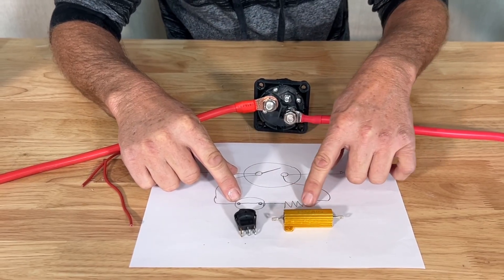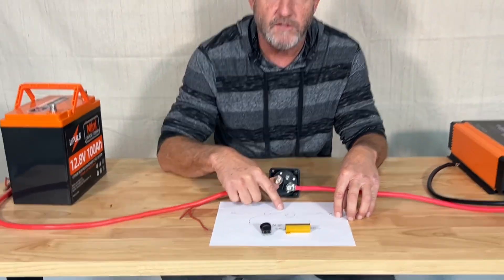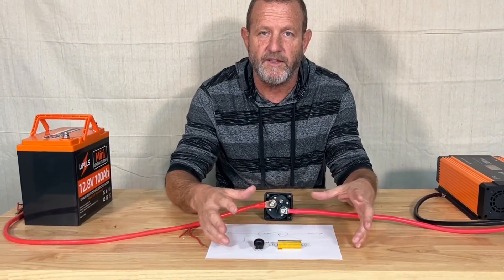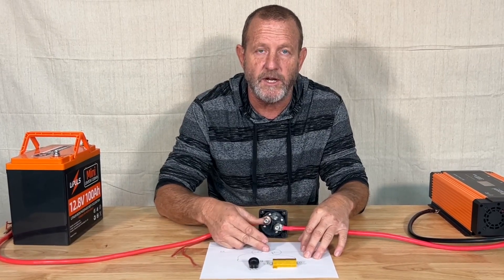through the resistor, so it slows the inrush down, capacitors are charged. The switch is still open, you can let that off, you got a few minutes before those capacitors will drain down, and you shut this switch.